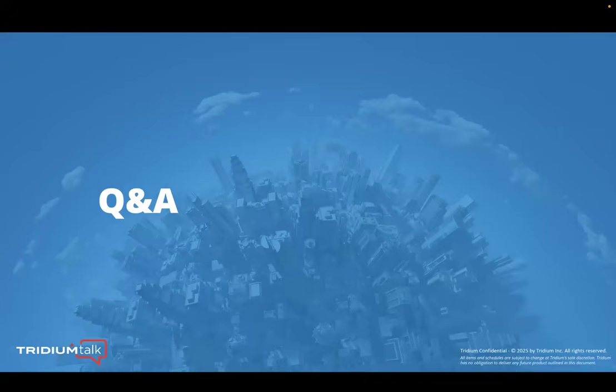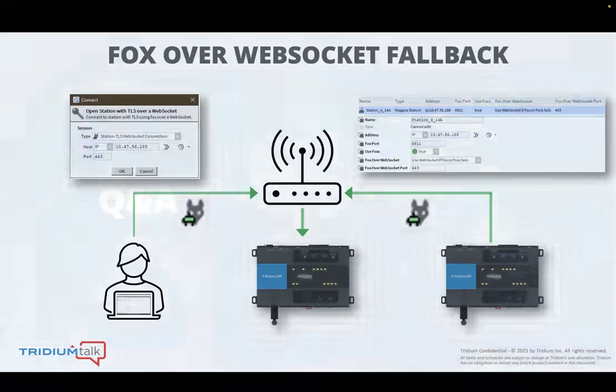So those bookmarks or hyperlinks that you have when navigating in Workbench may fail if you cut off port 4911 or you're turning off FoxS or something, and so it wouldn't connect to those stations. But the nice thing about the fall through is you don't have to then go change all those bookmarks. It will detect that it can't make that connection because that port's not available, and it'll fall through and make the Fox over WebSocket connection.